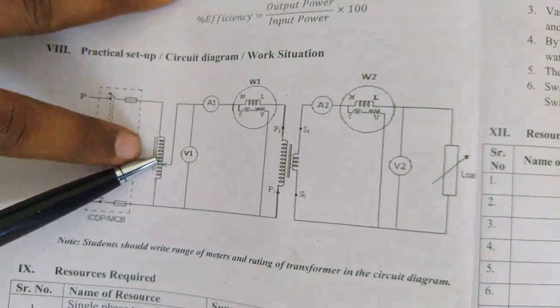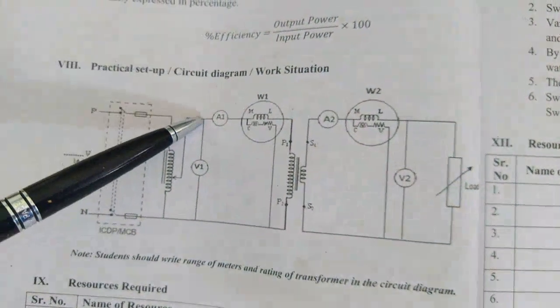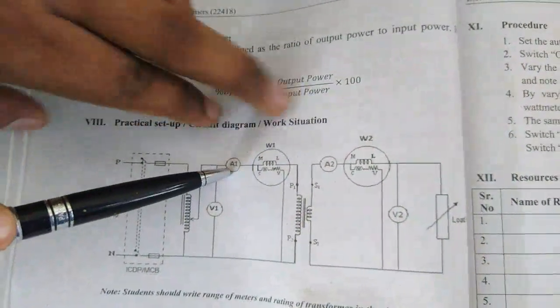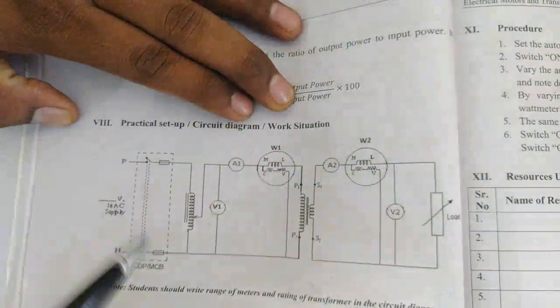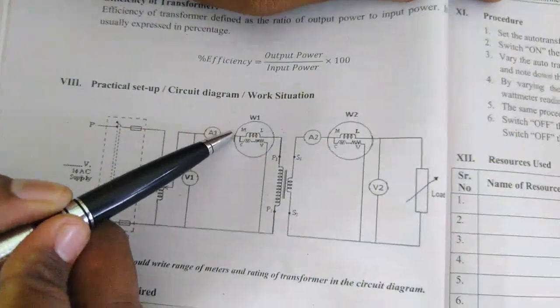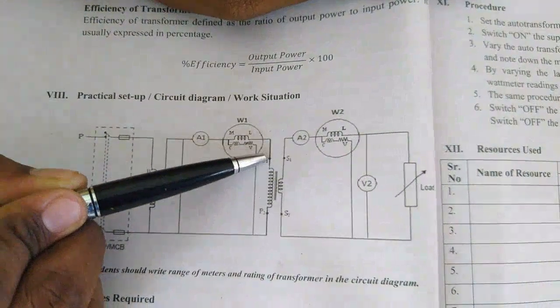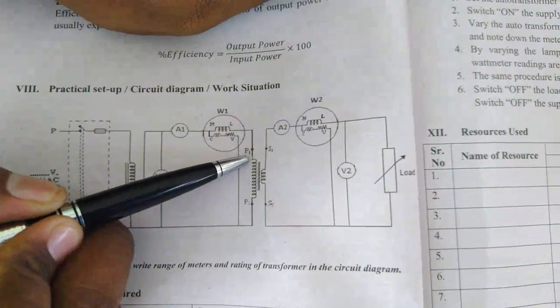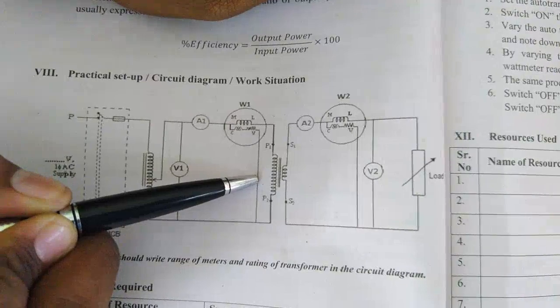This is the actual circuit diagram. This is the input supply connected to a single phase variac. One point of the single phase variac is connected to the primary of the transformer through an ammeter and wattmeter. The ammeter's second point is connected to the wattmeter M point. The wattmeter M and C points are short circuited, and the L point is connected to the transformer primary, which has a larger number of turns. This is a step-down transformer.